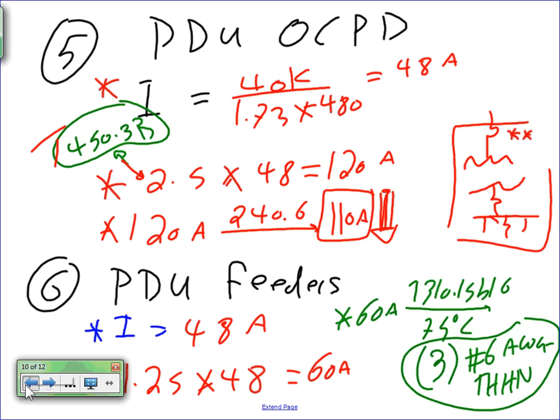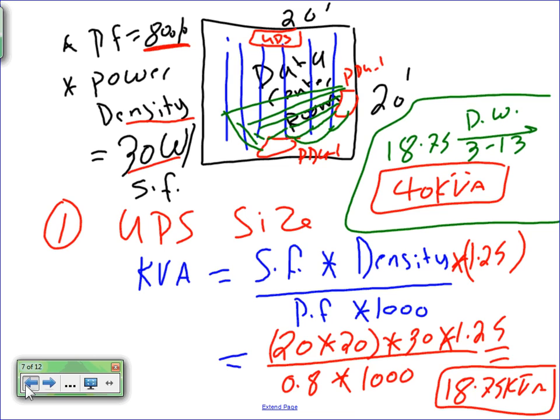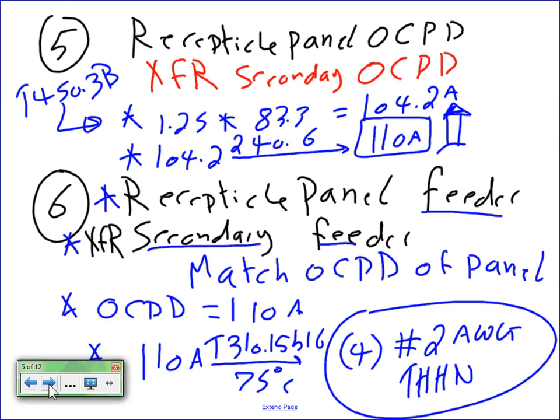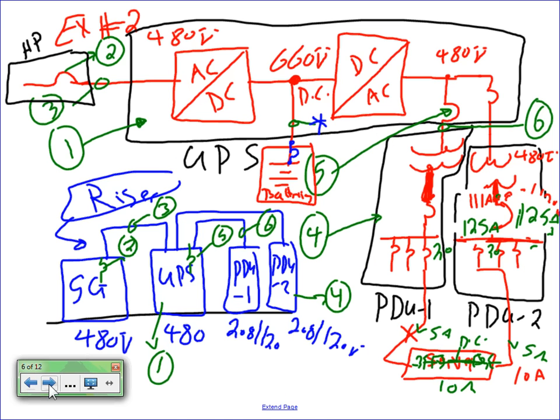So let's go back and review with all this stuff, guys. Number 7 is going to be okay. If you look at what we did, we sized the UPS, the feeder to the UPS and overcurrent protection device. Then we sized the PDU, the feeder that feeds the PDU and overcurrent protection device. And then it's done. Now, what we didn't size here, guys, is the panel and this side.